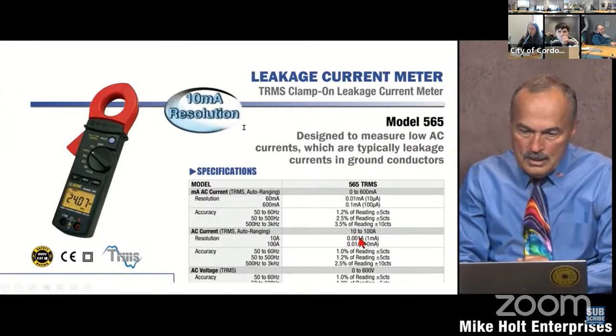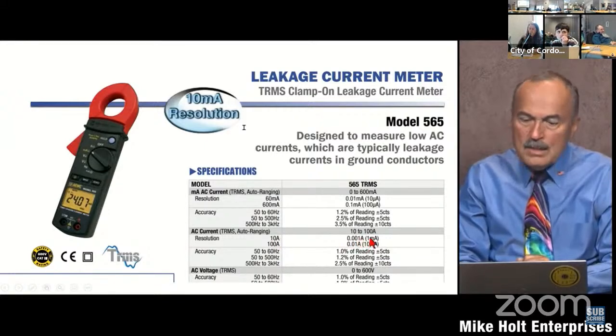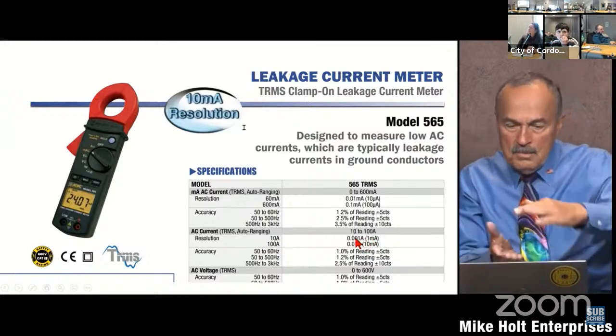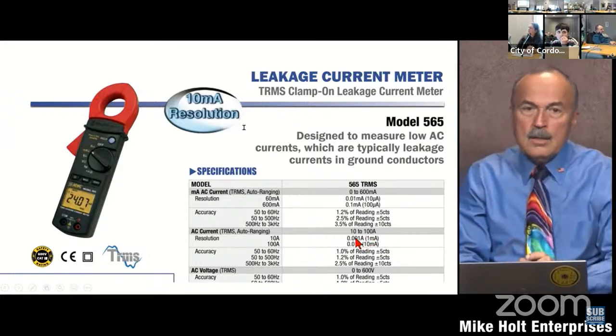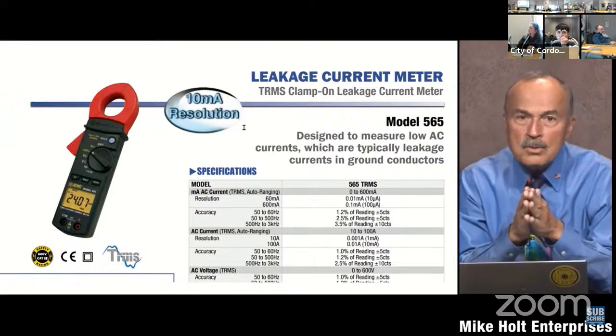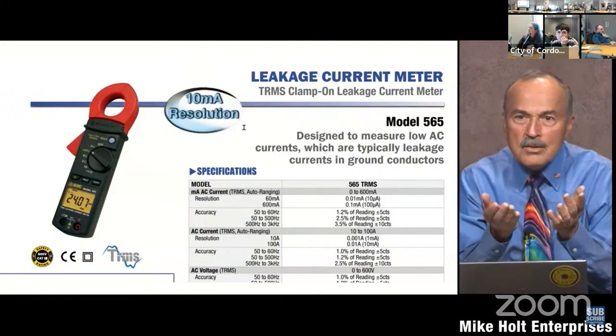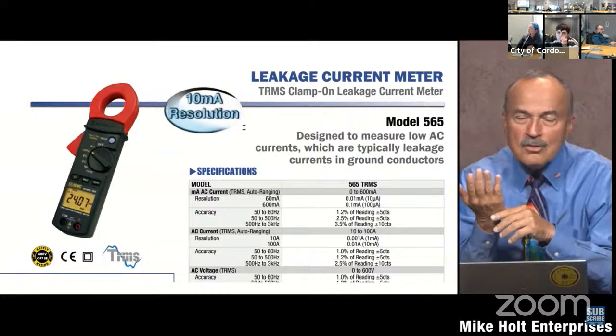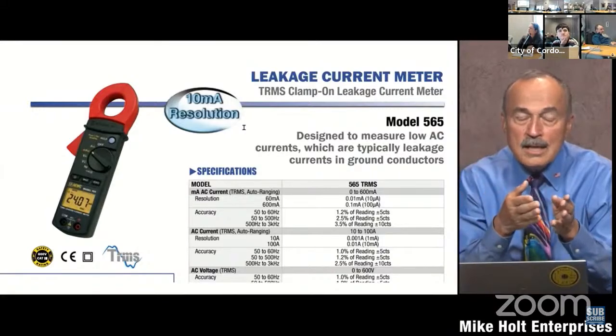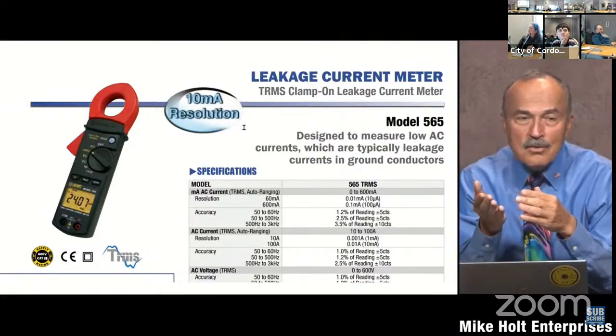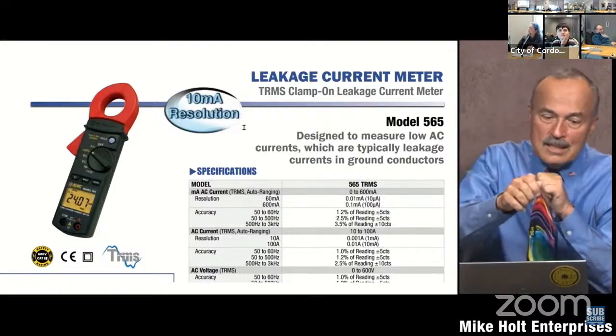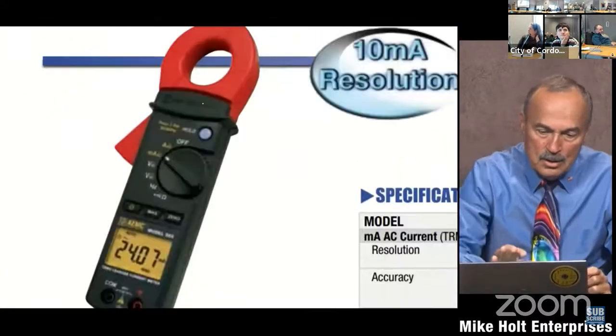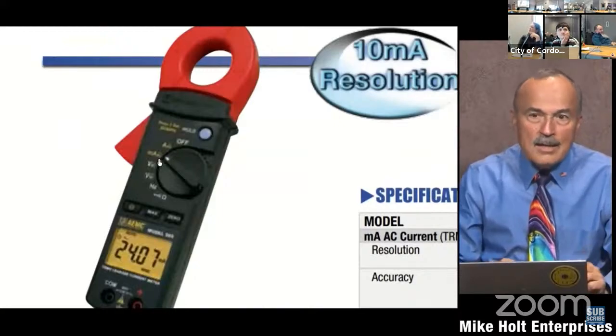Oh, hey, here it is, the accuracy down here. Whatever it is, I can't see. I think I'm missing some information down here. This will measure milliamperes. You can't take a regular ammeter that's set at a 200 amp range, and it has a 1% accuracy, and now you're at 200 amps. Well, then you need to set this into the milliamp range at 1 or 2%. Well, yeah, now that's going to pick it up.